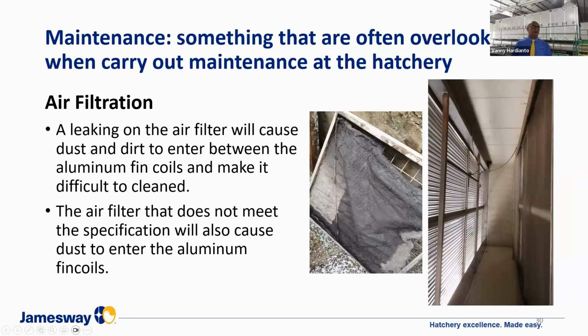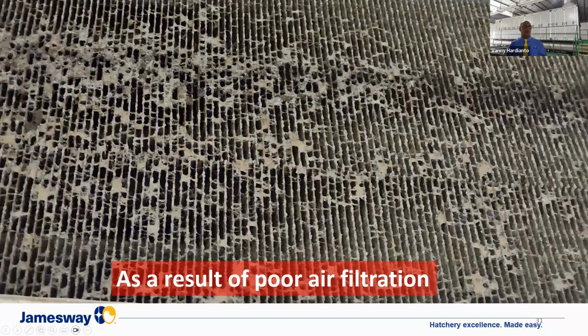A leak in the air filter will cause dust or dirt to enter between the aluminum fins of the coil and make it difficult to clean. An air filter that does not meet the specification will also cause dust to enter the aluminum fin coil. Here is an example of dust entering the aluminum fin coil. When it goes deeper, because sometimes the cooling coil is quite thick, it's really difficult to clean.